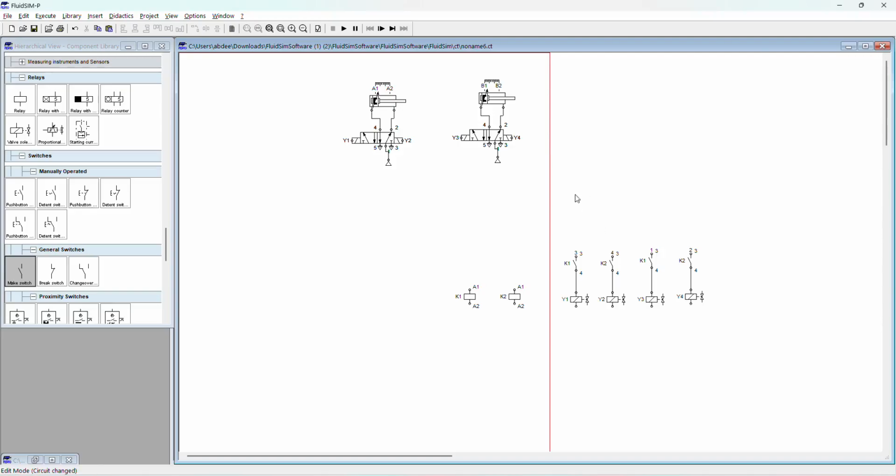Yes. So now we said that each solenoid will be activated by a normally open switch and deactivated by a normally closed switch that corresponds to the limit switches we can see here. Exactly similar to what we used to do in the pneumatic stuff. All right? So we do the same thing for all solenoids, and we do the connections before we name them.